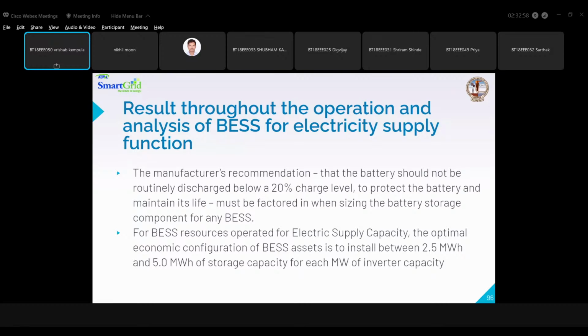The manufacturer's recommendation that the battery should not routinely discharge below a 20% charge level, to protect the battery and maintain its life, must be factored in when sizing the battery storage component for any battery energy storage system.